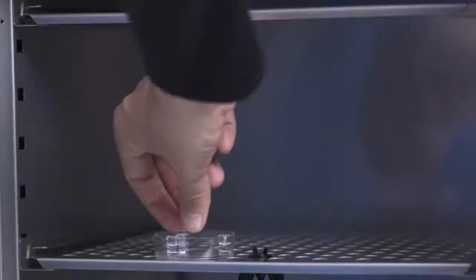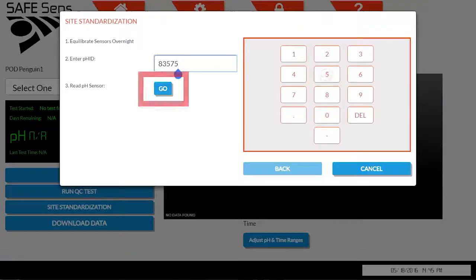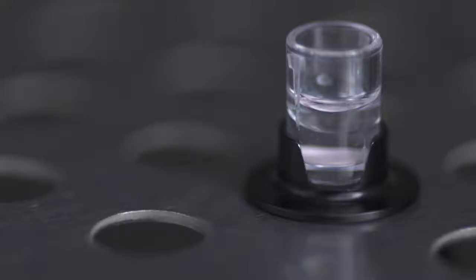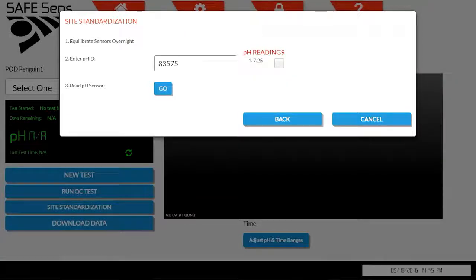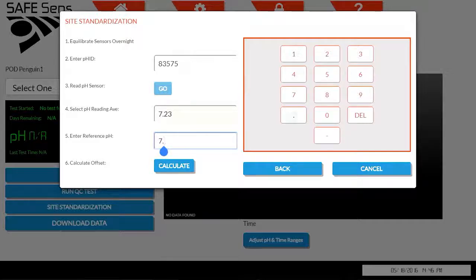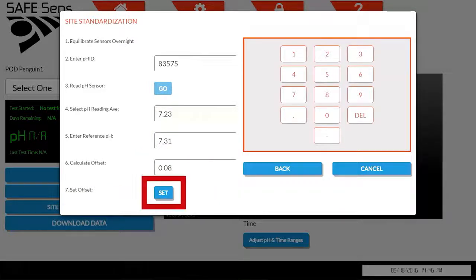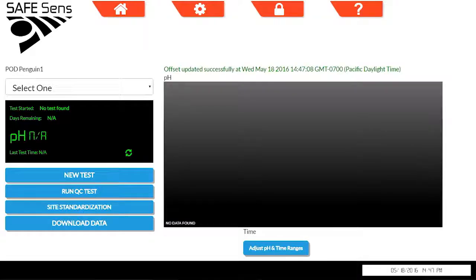Then, quickly read all the sensors by placing them on the probe and pressing Go for each sensor. If a few readings are done incorrectly, don't worry. After you have read the sensors, you can select the ones which you wish to average. If a reading or two was done incorrectly, don't select that one for averaging. After getting an average, enter your reference pH and press Calculate. Your offset will be calculated, and you can then set it into your TrakPod with the Set button. This completes the site standardization protocol for this TrakPod. The protocol can be repeated with the same sensors in a second incubator, but you must allow at least 1 hour for the sensors to equilibrate in the second incubator's environment.